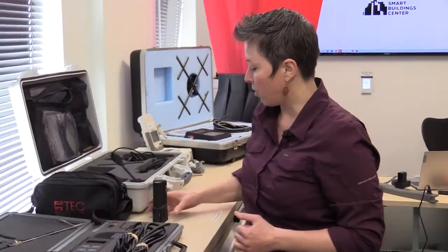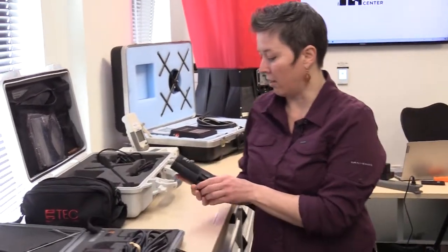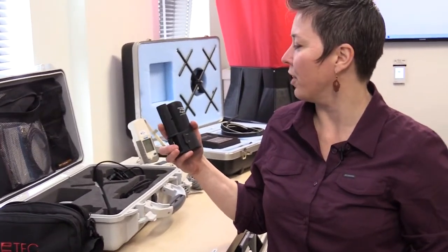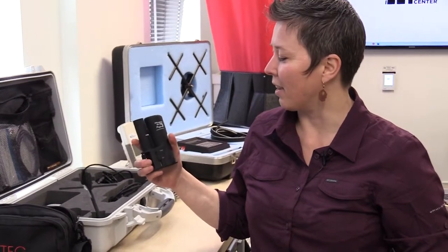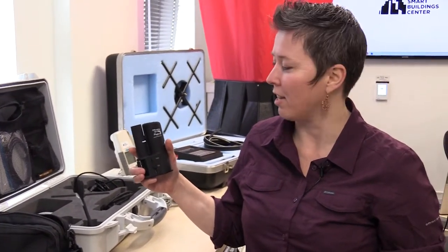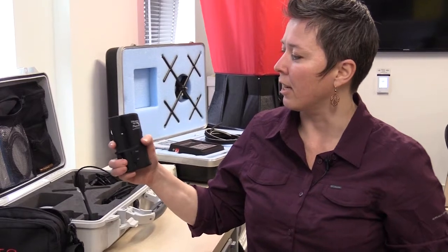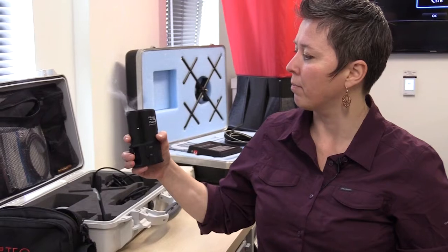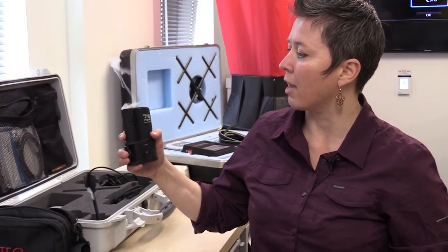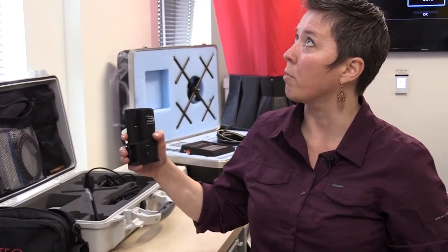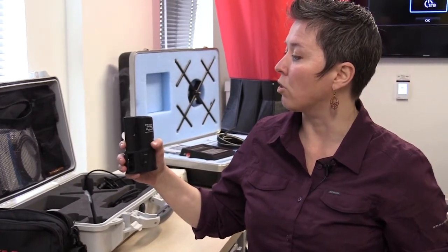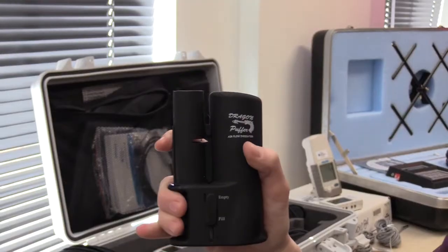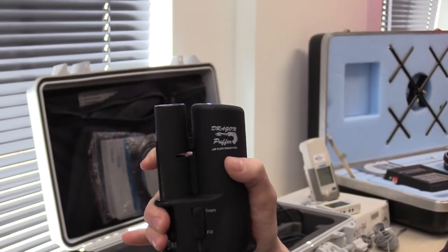And another tool we have here is the smoke pencil. This is called the Dragon Puffer, and it's basically just like a mini smoke machine. So you make a little puff here, and it can help you determine which way the air is going. This can be used standalone to see where you might be getting drafts, which direction of flow, making sure you have the correct pressure, positive or negative, depending on the space.